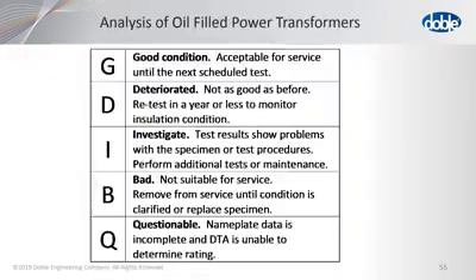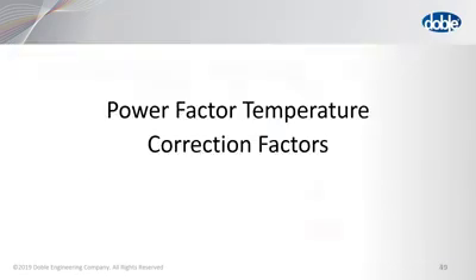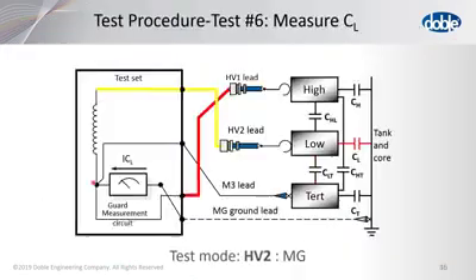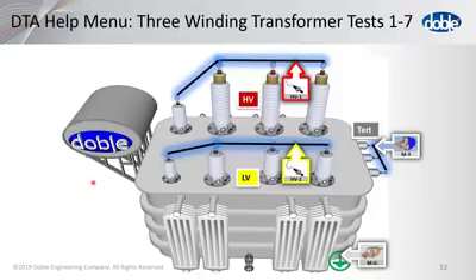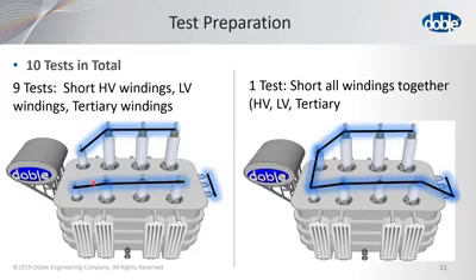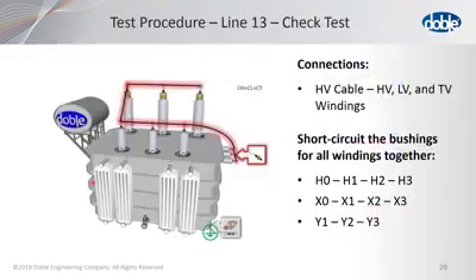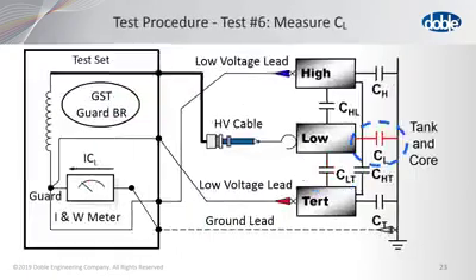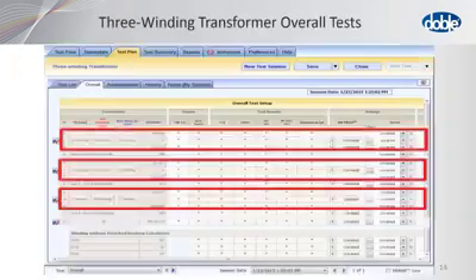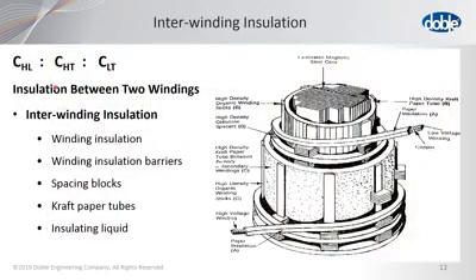In the insulation circuit, there are no bushings listed during the interwinding tests, and that's because they are not included. Is that when I'm energizing the high voltage winding and I'm going to the low voltage winding, of course, it's done as a UST test, right? Well, anything that is grounded during a UST test is not measured. So the bushings are not tested during the ungrounded specimen test. Yeah, here it is right here. Notice that in this list, for any of the interwinding insulations, there are no bushings tested. And that's because when you go from the bushing center conductor to ground, that is being guarded away. So the bushing, in effect, disappears during the interwinding test.